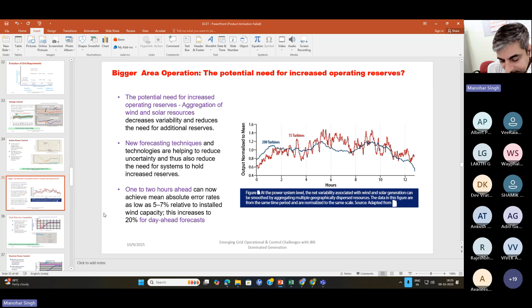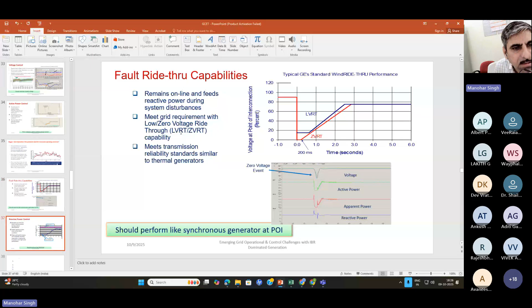These resources must also be equipped with fault ride-through capability, which is now a mandatory requirement. Earlier, whenever there was a fault, these resources would simply get disconnected from the grid. Now, since their population is very high, they must handle the fault load and stay connected, with fault ride-through for both low voltage and high voltage, along with reactive power control capabilities, which are very important.